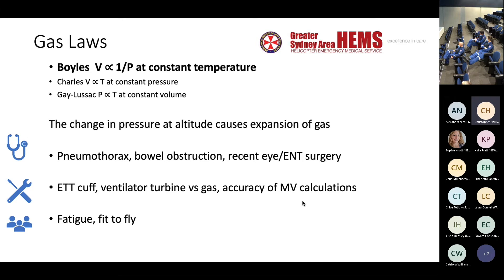For very long jobs or international retrievals — like the care flight jobs you do — you need to bear in mind that you need an adequate gas supply and adequate power supply. The literature also mentions that the accuracy of tidal volume and therefore minute volume calculations varies between ventilators once they're exposed to altitude. I'm sure that was a consideration in choosing the Hamilton.